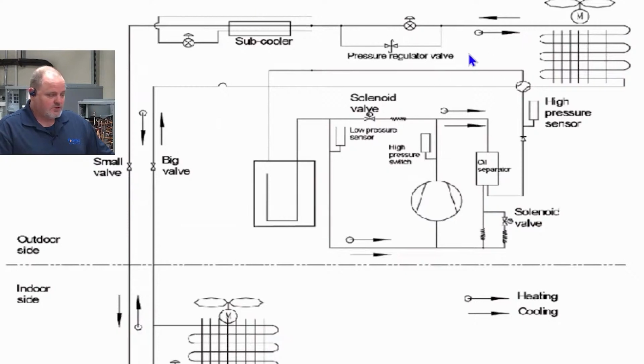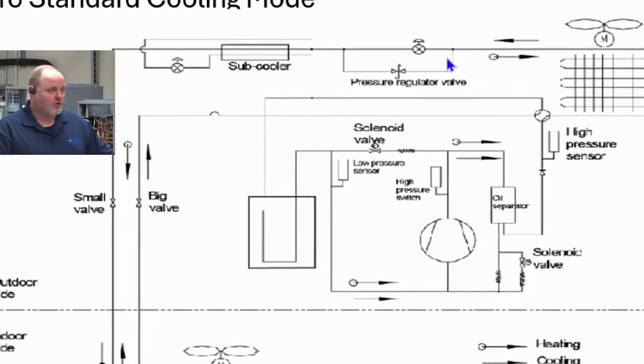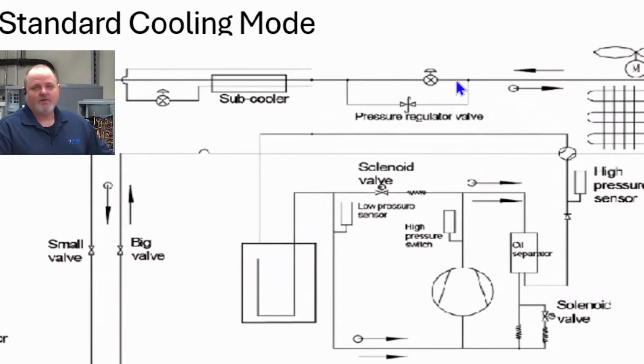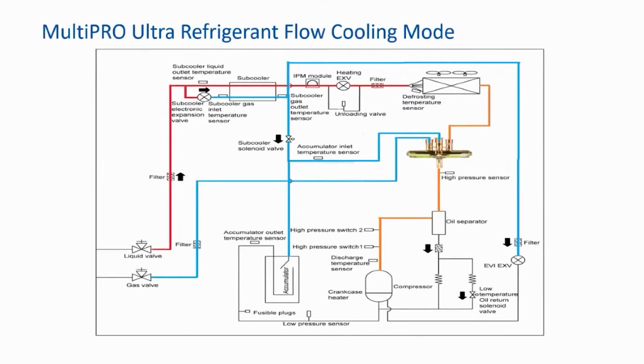And once he took the side panel off of there, and I told him to look for these EEVs, he found that coil just hanging there. We put the EEV coil on that valve body and had that machine up and running with no issues. So doing a simple inspection would have solved that. Right. Yeah. So this piping diagram, I want to talk about this some more as well.